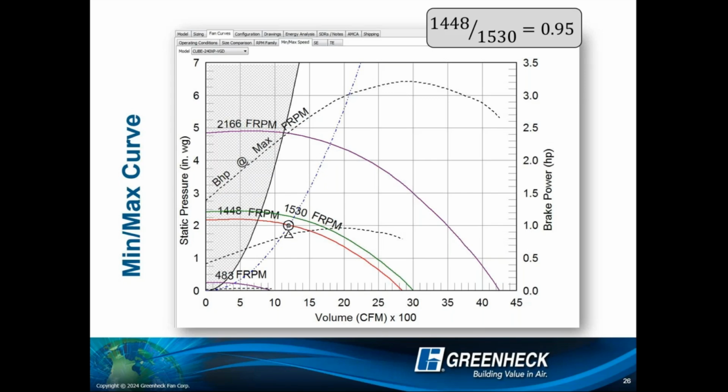I like making selections where I'm at 80%, right? I've got a solid 20% to turn up, and usually about 60% to turn down. That's my conservative viewpoint as an engineer. So if you can take that guidance and maybe develop, either for your firm or for you, what is your comfort zone? And like I said, for me, my comfort zone depends on the project.